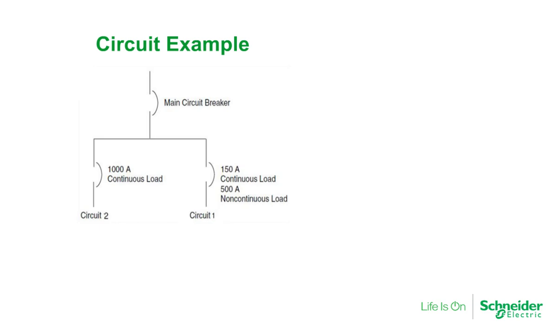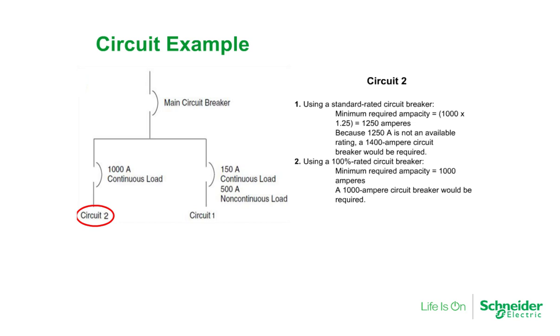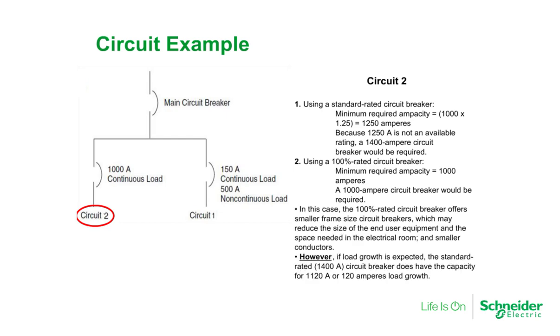Now let's take a look at circuit number 2. When using a standard rated circuit breaker in circuit number 2, the minimum required ampacity calculation would be 1000A times 1.25, yielding 1250A. Because 1250A is not an available rating, a 1400A circuit breaker would be required. Using a 100% rated circuit breaker, the minimum required ampacity would simply be 1000A, so a 1000A circuit breaker would be required. In this case, the 100% rated circuit breaker offers a smaller frame size circuit breaker, which may reduce the size of end user equipment and the space needed in the electrical room, plus smaller conductors.